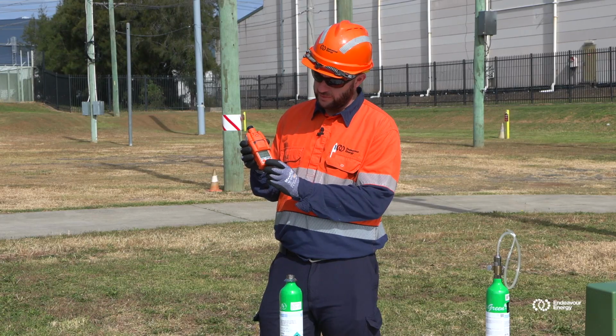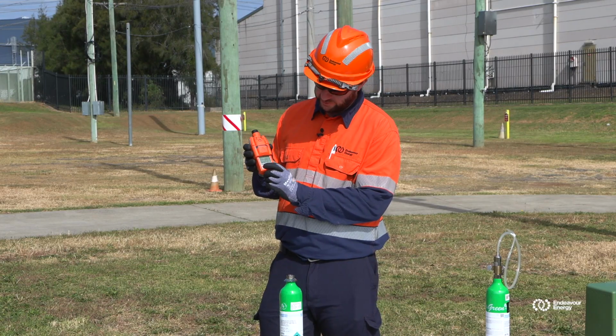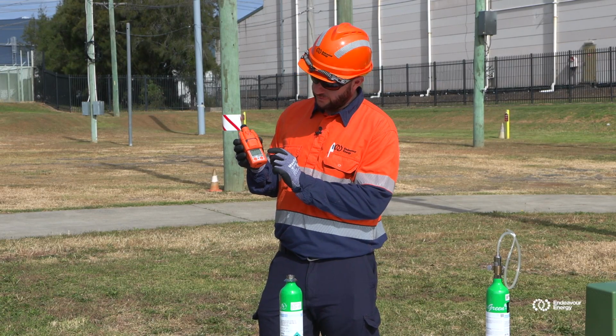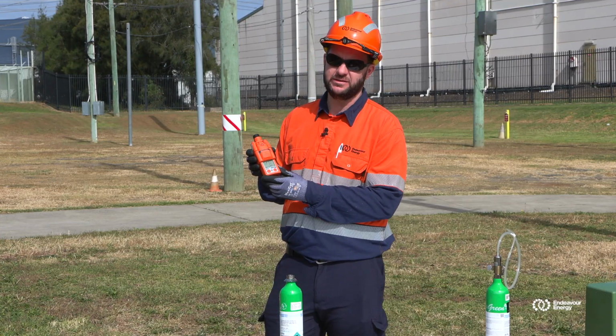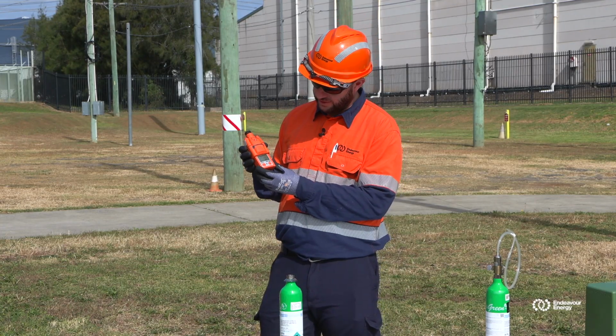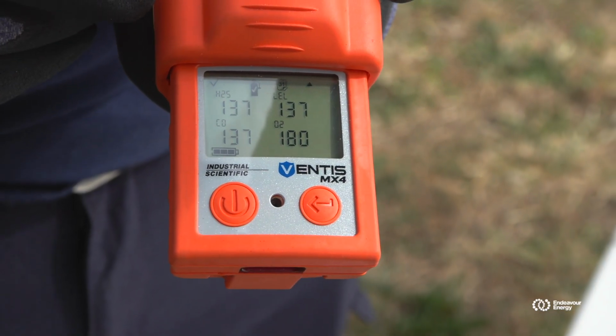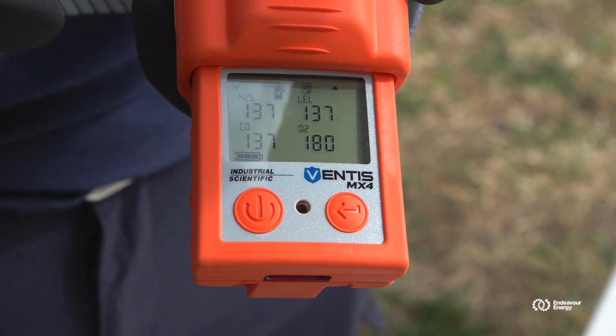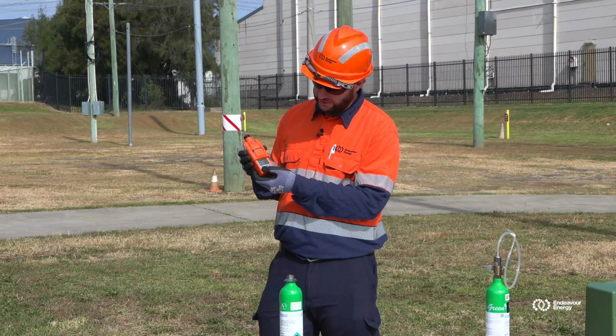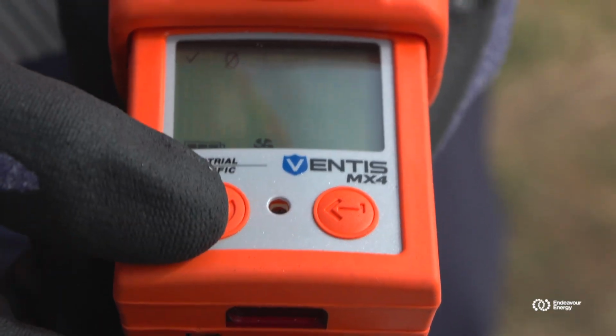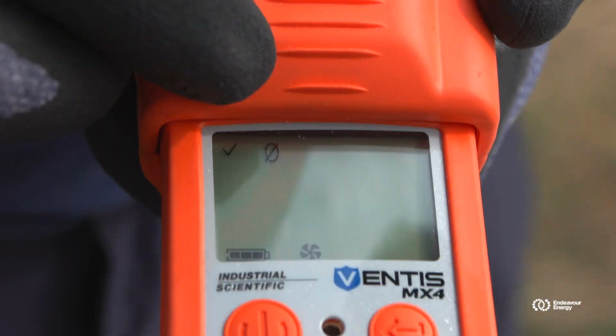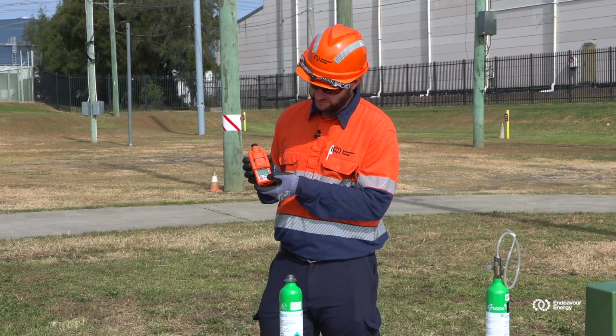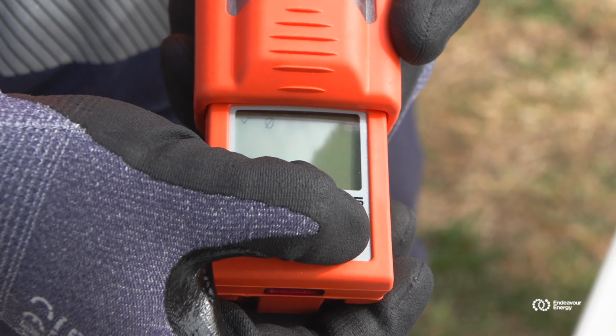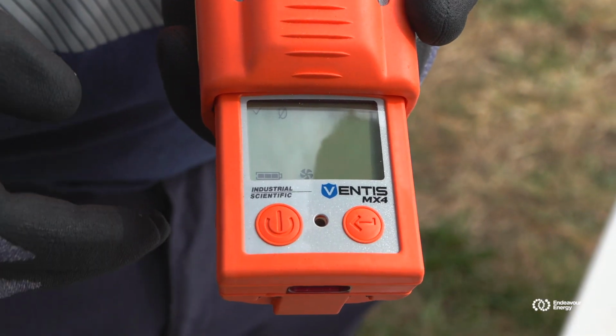To get to the zero menu, we're going to press the power button. We scroll through. The first screen here will show us the days till the sensors require calibration again. So we have H2S 137, LEL 137, carbon monoxide 137, oxygen 180. Press the button once again. We'll get to the zero screen here. We're going to press and hold the return key for a second. Now our readings will be at zero.